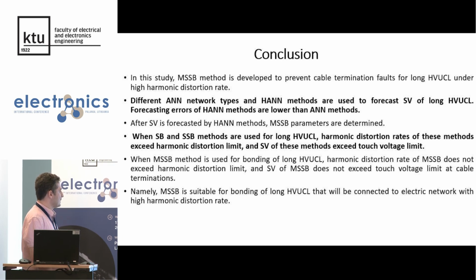After SV is forecasted by HANN methods, MSSB parameters are determined. When SB and SSB methods are used for long high voltage underground cable lines, harmonic distortion rates of these methods exceed the harmonic distortion limit, and SV of these methods exceeds the touch voltage limit.